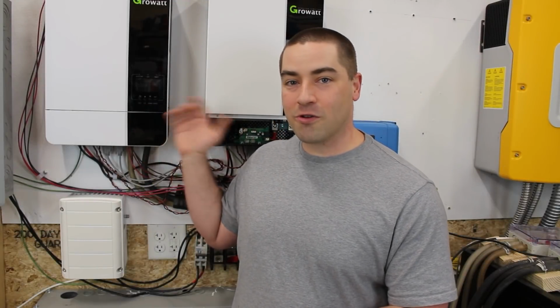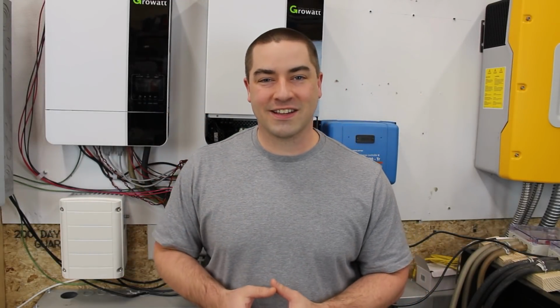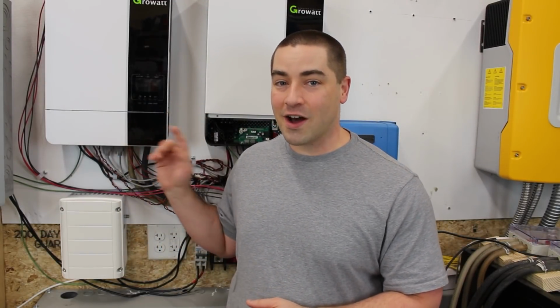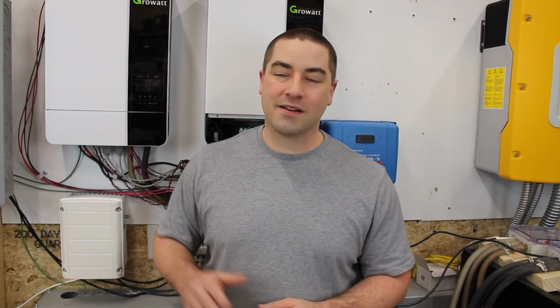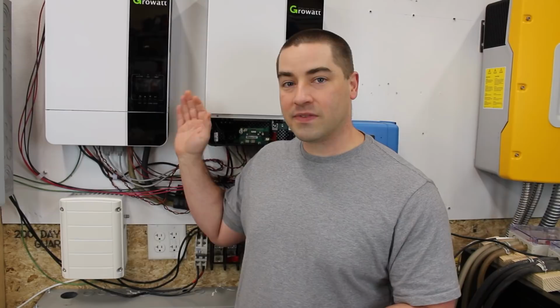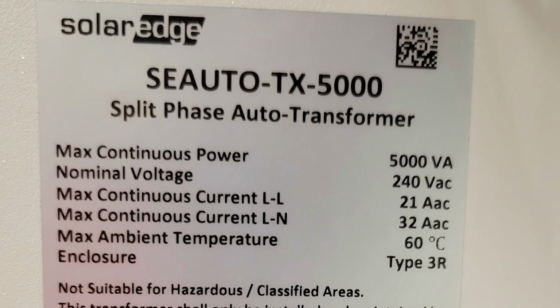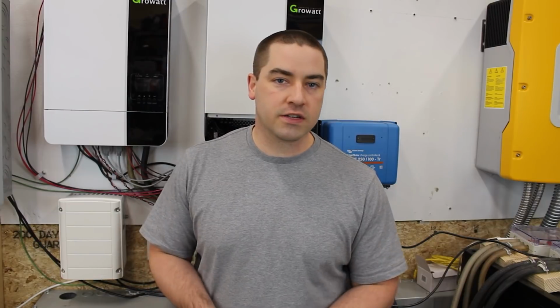So I've been running 2 Growatt inverters, which is a total of 10 kilowatts. I have them turned off right now because they make some fan noise, which would really mess up the audio for the video. Each inverter is 5 kilowatts. The auto transformer that I'm using is a 5 kVA from SolarEdge. They're getting harder to find, so Signature Solar has sourced some more from Growatt. They're still 5 kVA, still auto transformers, so they basically do the same job.